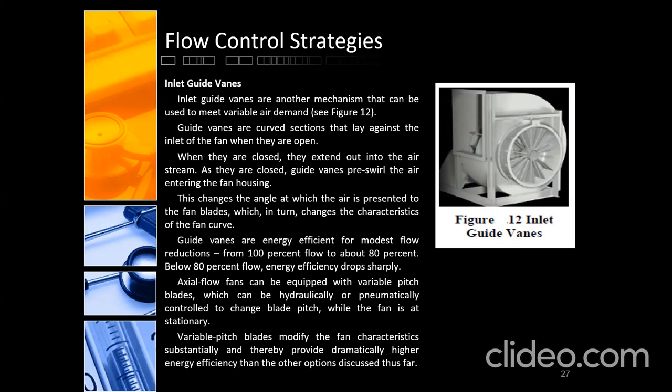Okay. Axial flow fans can be equipped with variable pitch blade, which can be hydraulically or pneumatically controlled to change blade pitch while the fan is at stationary. Variable pitch blade modify the fan characteristics substantially and thereby provide dramatically higher energy efficiency than the other options discussed thus far.